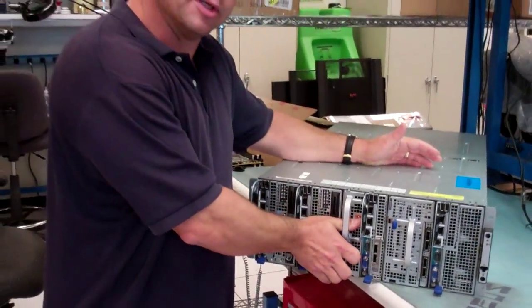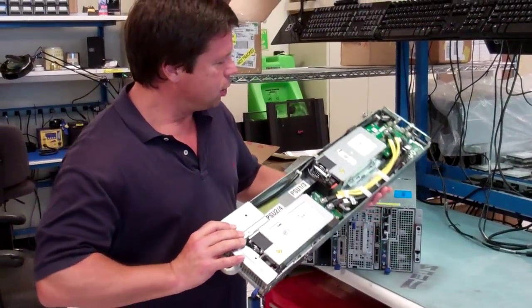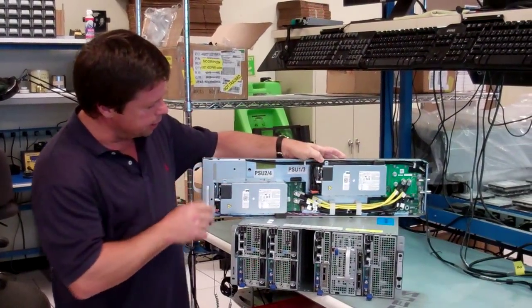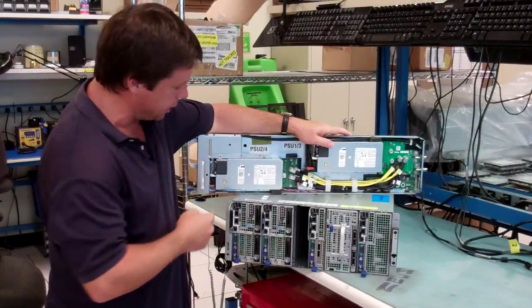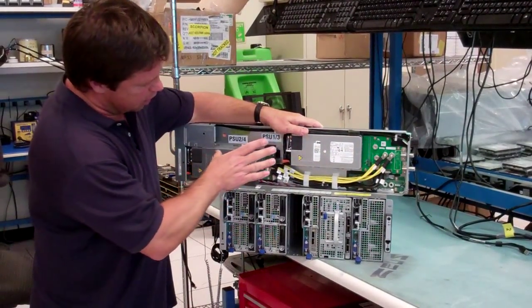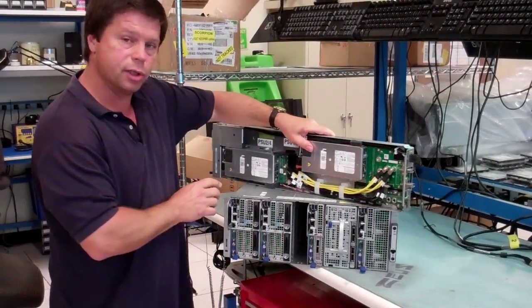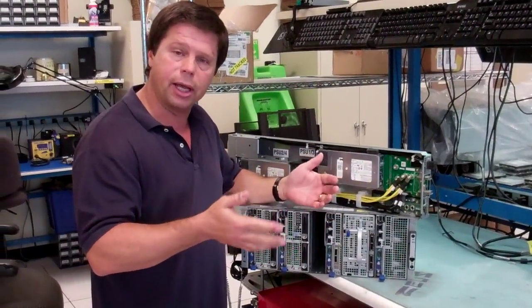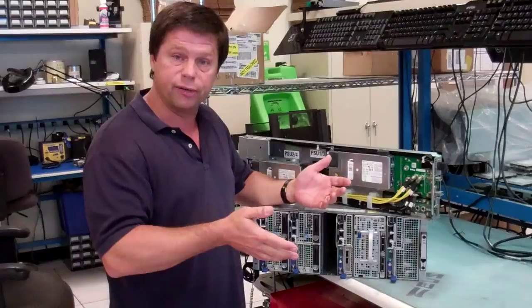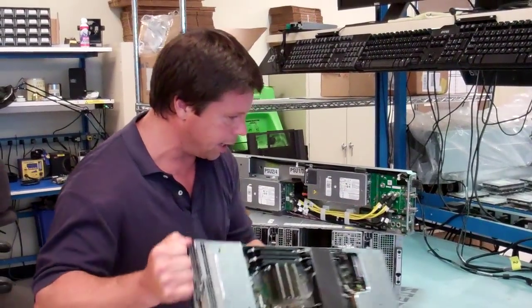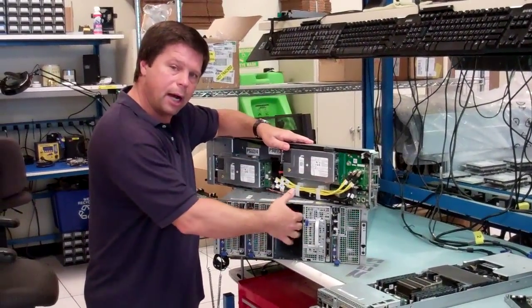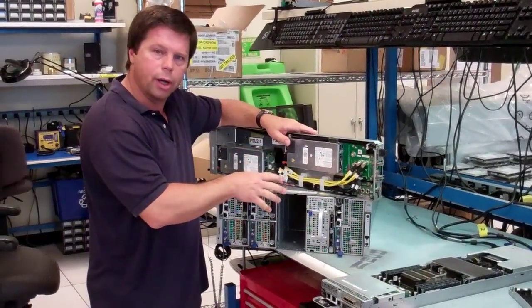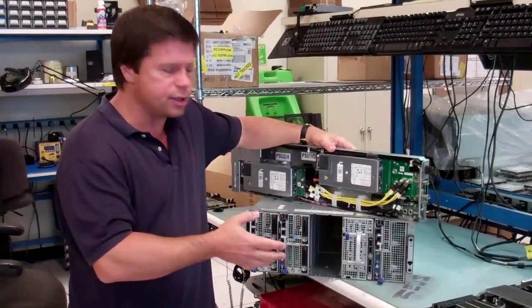We have our power supply sled. And what we've taken is two very industry standard 1,400-watt supplies. And we've arranged them such that we can put two in a single wide. And in fact, back to that comment I made about being able to handle both an A and a B grid feed, we could sacrifice this single wide and have two power sleds. So it's kind of a 1 plus 1 at roughly 2800 watts.